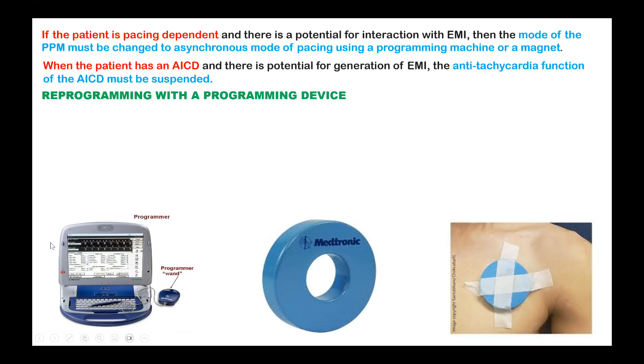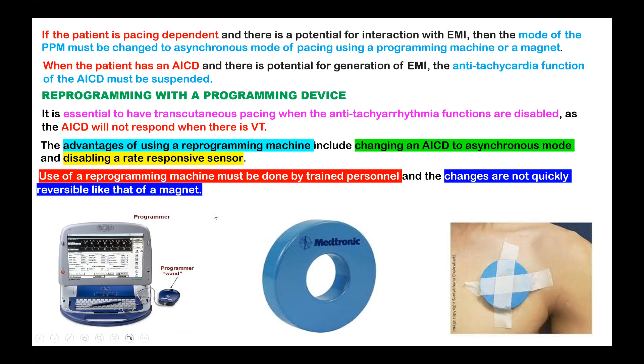So reprogramming with a programmer device is essential to have transcutaneous pacing available when the anti-tachycardia function is disabled, as the AICD will not respond when there is a ventricular tachycardia. And the advantages of using a reprogramming machine include changing the AICD to asynchronous mode and disabling the rate responsive sensor. And at the same time, you can reset it after the procedure also. So using a reprogramming machine must be done by trained personnel, and changes are not quickly reversible like that of a magnet. So here, if you remove the magnet, it reverts to the original setting. But with programming, you have to reset the whole thing if you want to get back to the old setting.